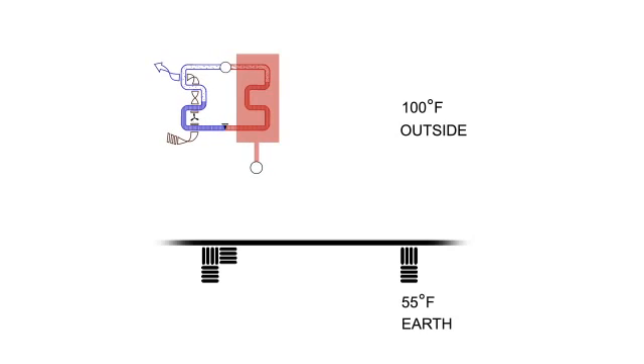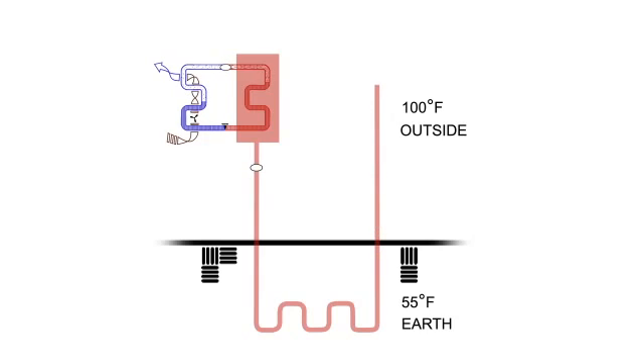So we replace the hot air with the mild 55-degree water, cooled by a water loop moving through the ground. The compressor simply doesn't have to create the level of high pressure required to condense in 100-degree air when the condenser is instead bathed in 55-degree water.